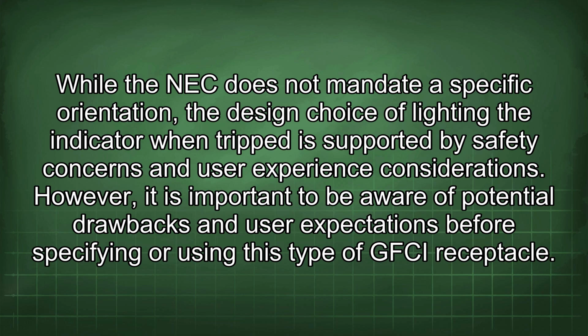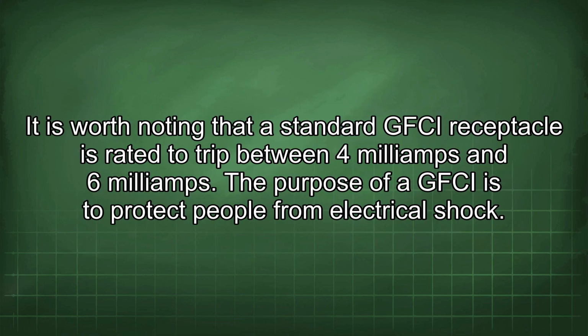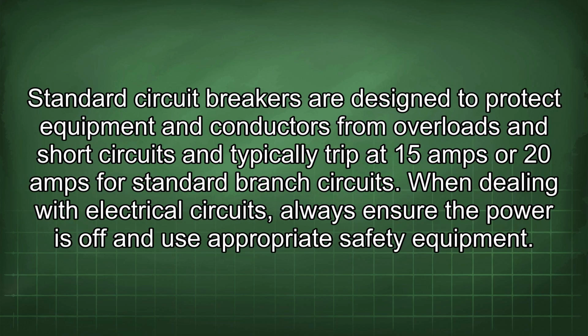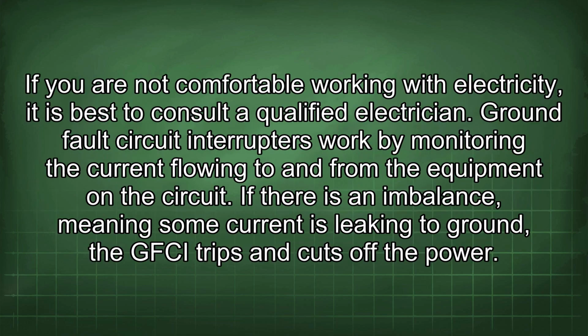GFCI receptacle. It is worth noting that a standard GFCI receptacle is rated to trip between 4 mA and 6 mA. The purpose of a GFCI is to protect people from electrical shock. Standard circuit breakers are designed to protect equipment and conductors from overloads and short circuits, and typically trip at 15 amps or 20 amps for standard branch circuits. When dealing with electrical circuits, always ensure the power is off and use appropriate safety equipment. If you are not comfortable working with electricity, it is best to consult a qualified electrician.